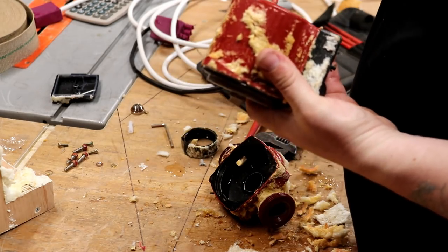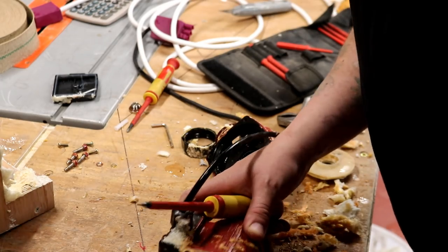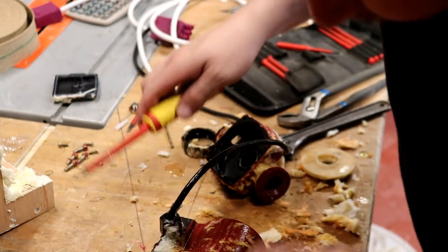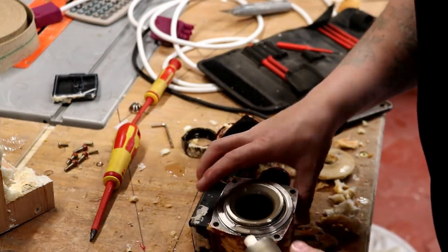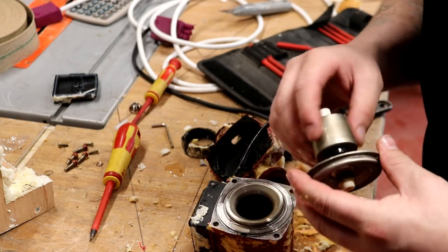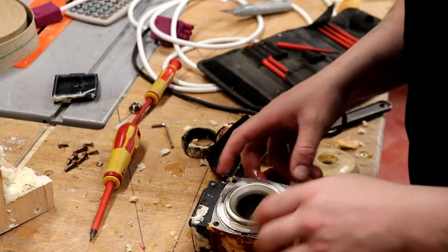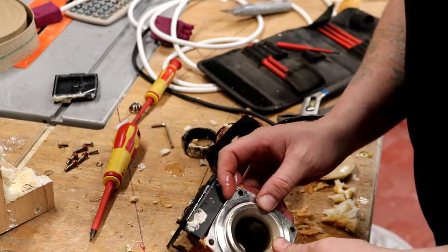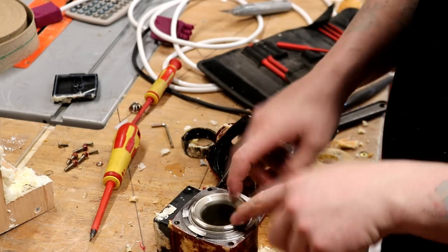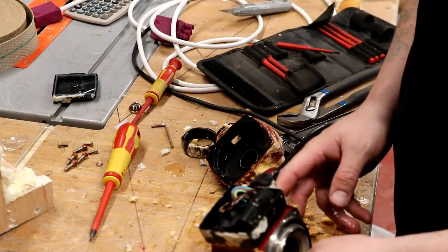Yeah, I wonder if that comes out then. Well, that's a big seal, that. It's quite a deep ring. Here we are. So that is a flooded chamber. So you do have your glycol, everything else in this flooded chamber. So I bet you that that, as a motor, would still work. Maybe it's just burnt out the capacitor.